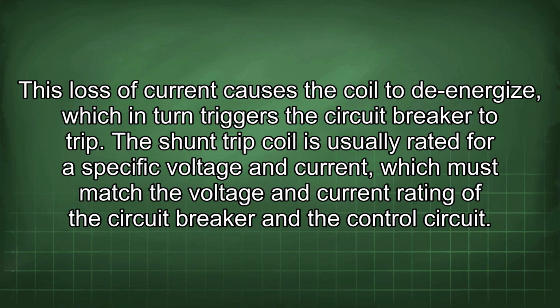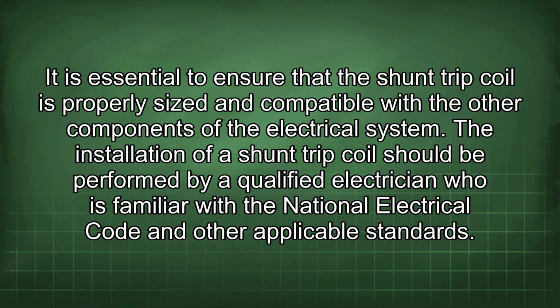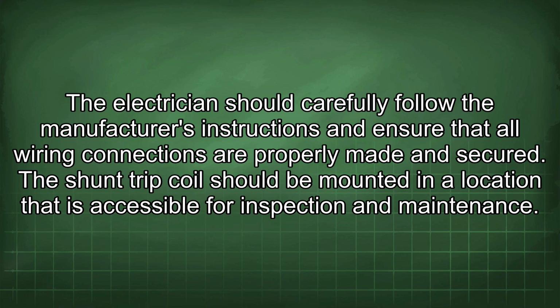The shunt trip coil is usually rated for a specific voltage and current, which must match the voltage and current rating of the circuit breaker and the control circuit. It is essential to ensure that the shunt trip coil is properly sized and compatible with the other components of the electrical system. The installation of a shunt trip coil should be performed by a qualified electrician who is familiar with the National Electrical Code and other applicable standards. The electrician should carefully follow the manufacturer's instructions and ensure that all wiring connections are properly made and secured. The shunt trip coil should be mounted in a location that is accessible for inspection and maintenance.